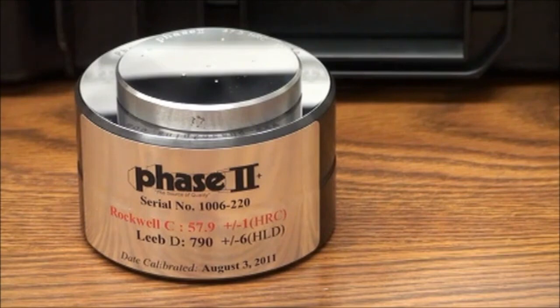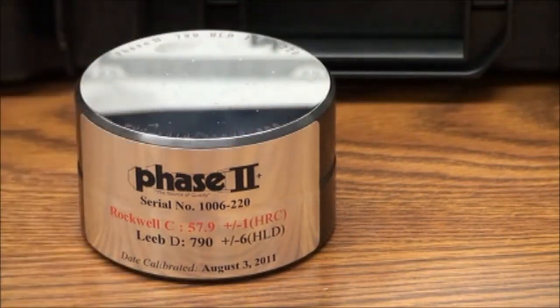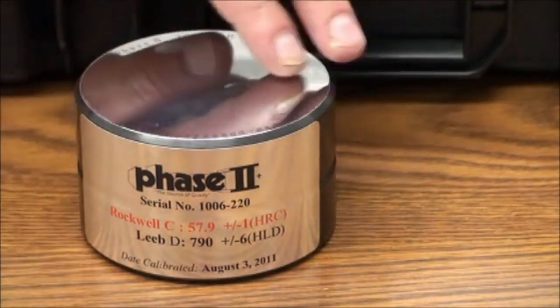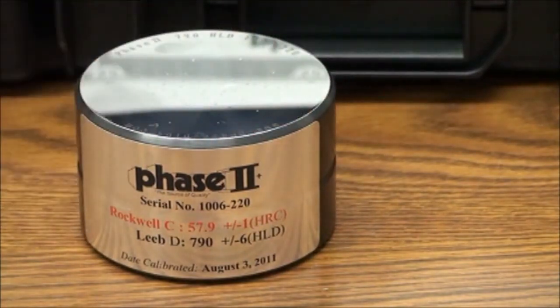portable hardness testers. The next parameter is surface roughness. Surface roughness should average a 2 micron or 80 micro-inch finish or better, using the standard impact probe. Optional probes such as the G probe can handle rougher surfaces such as on rough castings.